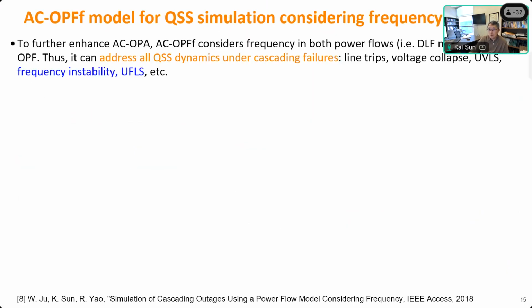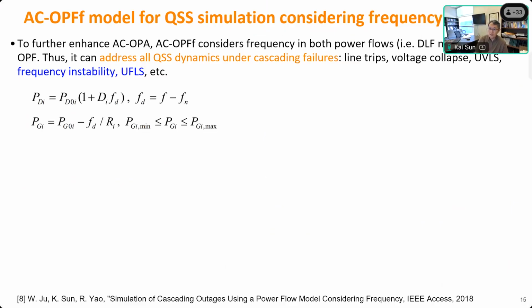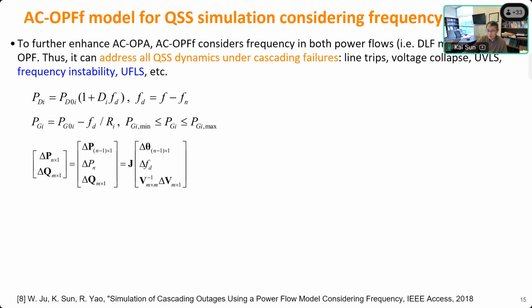These slides give you one idea to still use the AC OPA model, which is a steady state model, but we add frequency regulation into the model. So we don't run any time domain simulation. We want to capture the quasi steady state behavior of the grid, and the cascading failure can cover line trips, voltage collapse, voltage load shedding, frequency instability, and then frequency load shedding, without running time domain simulation. So the idea is to add the frequency dependent load model and the governor model into the power flow equation. You extend the power flow equation to add the frequency deviation to solve this frequency dependent power flow problem.